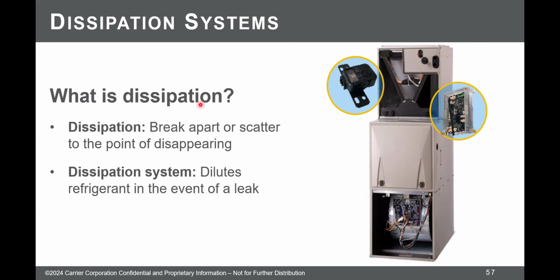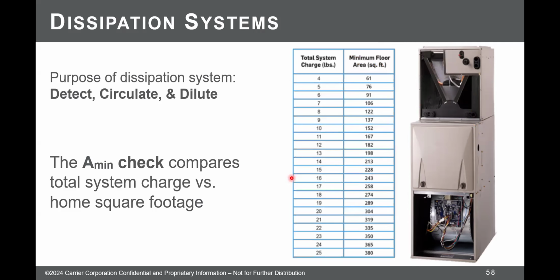On the outdoor unit, it's not a problem because on the outdoor unit, it's outdoors. So if there was a leak outside, it would have the whole earth to dissipate to. It'd be plenty of space. The inside is where things get limiting. So we have to have a space big enough, a house big enough, a building big enough, etc., for it to properly dissipate. So that's the passive dissipation. There's also going to be an active dissipation here in a second. So for the passive dissipation, if it's a split system, we'll look at how many pounds that the system was final charged with, and then there's a certain minimum square footage.